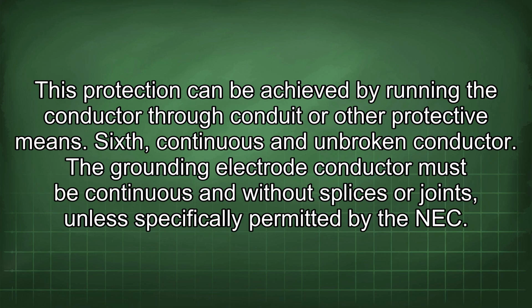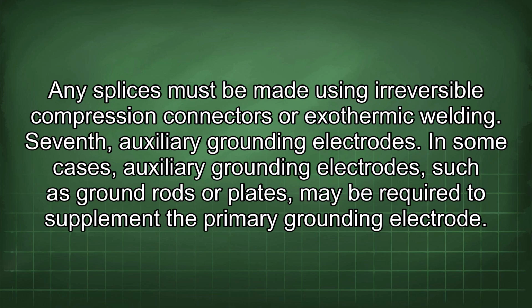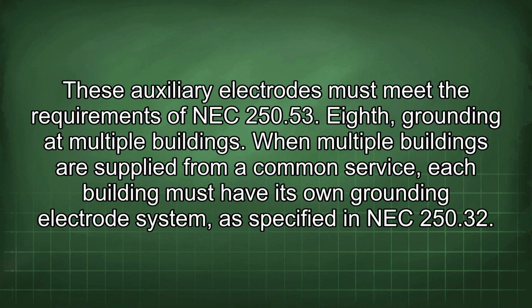Sixth, continuous and unbroken conductor. The grounding electrode conductor must be continuous and without splices or joints, unless specifically permitted by the NEC. Any splices must be made using irreversible compression connectors or exothermic welding. Seventh, auxiliary grounding electrodes. In some cases, auxiliary grounding electrodes, such as ground rods or plates, may be required to supplement the primary grounding electrode. These auxiliary electrodes must meet the requirements of NEC 250.53.